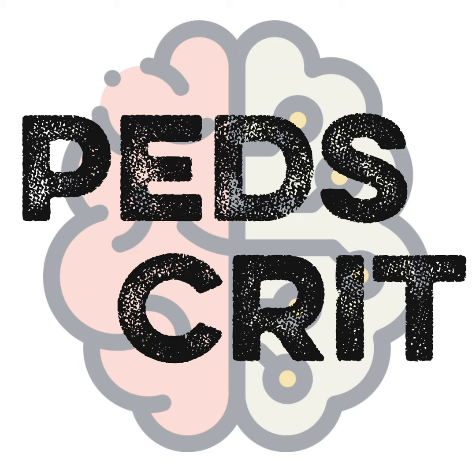Sometimes, despite our best efforts with flow trigger, we're still not able to capture them. And so that's the place where I will admit we don't use a ton of NAVA in our unit, but that's a place where I'm going to really turn to that and say, this is a patient who may benefit. Can we see about getting that to the bedside, get that catheter in? If we can just sense that electrical impulse from the diaphragm, that may be the only way that we can get a sensitive enough trigger to give the patient the breath when they want it.